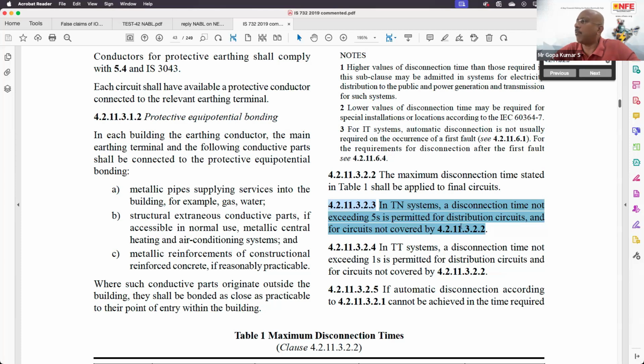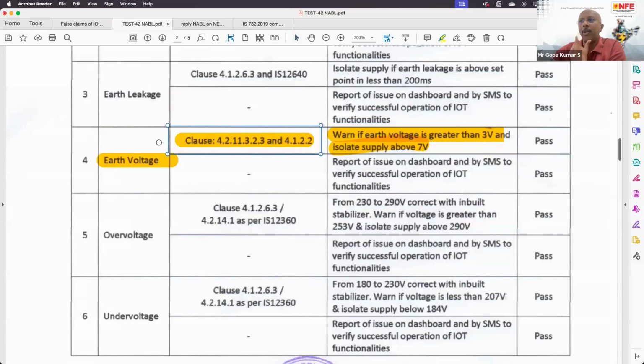for distribution circuits and for circuits not covered by 4.2.11.3.2.2. That means the distribution circuits, the final circuits up to 63 amps. Other than that, in TN system, a disconnection time of 5 seconds is permitted is the requirement in the IS 732 standard. Now the test report of this product says earth voltage, the clauses given there, if earth voltage is greater than 3 volt and isolate supply above 7 volt. The clause which is mentioned as well as the test which is mentioned, this has got no relation at all.